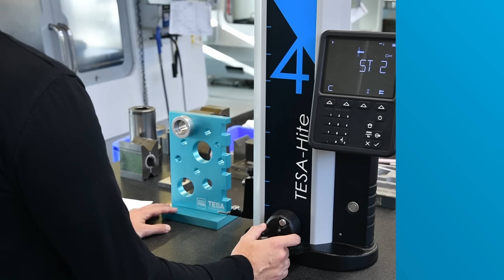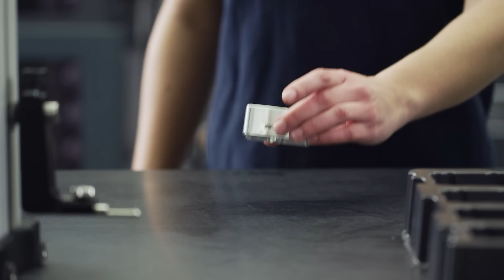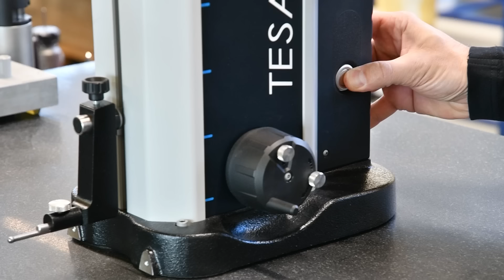Here we are talking about a typical practical use case, Tony. Most of the time during a measurement sequence, the part is moved and the height gauge stays still. The right hand is on the displacement wheel, displacing the probe up and down, and the left hand is on the part itself to move the part and to position the probe in the measurement area. But sometimes you need to move the instrument from one place to another on the granite surface, or you may face heavy or big parts to measure. So in these situations, you need to move the gauge itself.